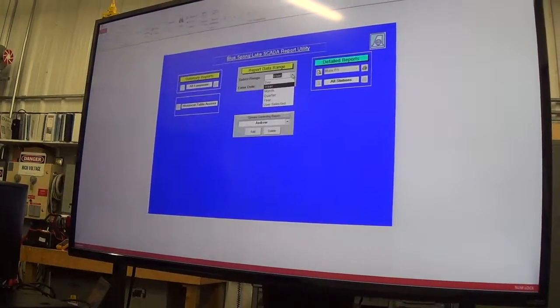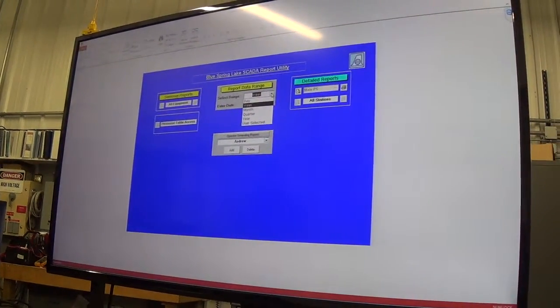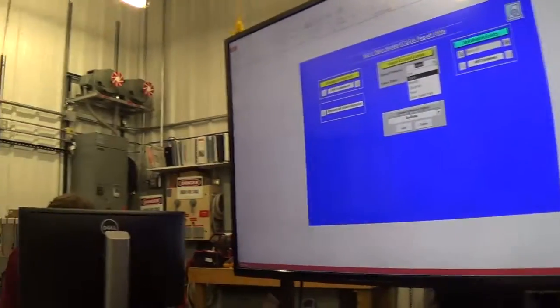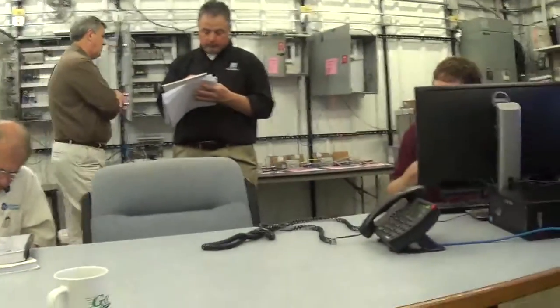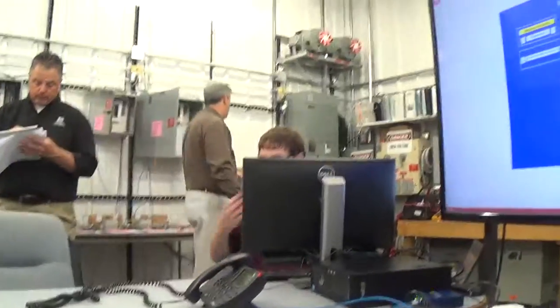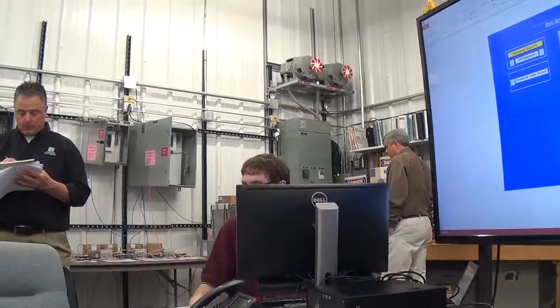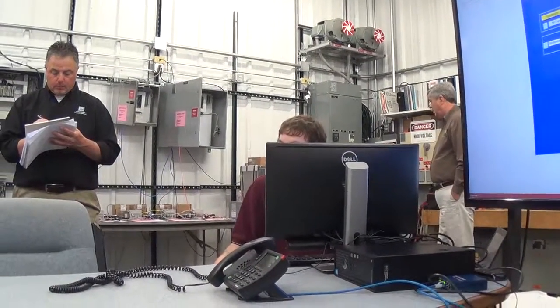And the reason why I was saying pulse versus flow rate, there's some minor difference in accuracy. When you use a flow rate over time, you may be off like 1% or something like that. The pulse rate is more exact. If it's a flow rate, we actually calculate it, whereas with a flow pulse, the flow meter actually calculates it for us, and the meter's capable of doing that.